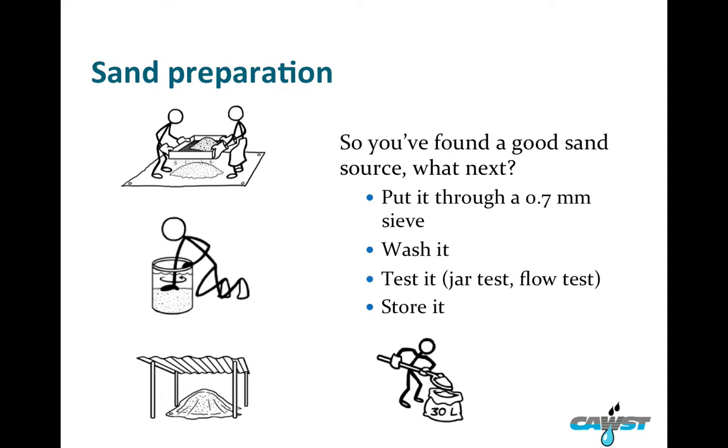Next, you would do a jar test, which I'll talk about in a second. Once you've completed many batches of sand, you would install a filter and check the flow rate. Once you're more experienced at washing sand, you should be able to tell quickly if the sand has been washed enough. But every load of sand you buy will be different. Always check the wash sand by doing jar tests and a trial installation.